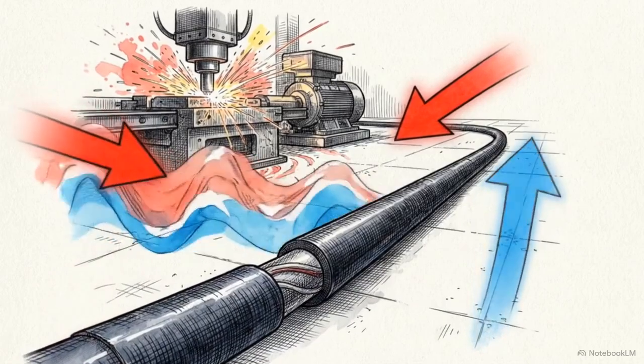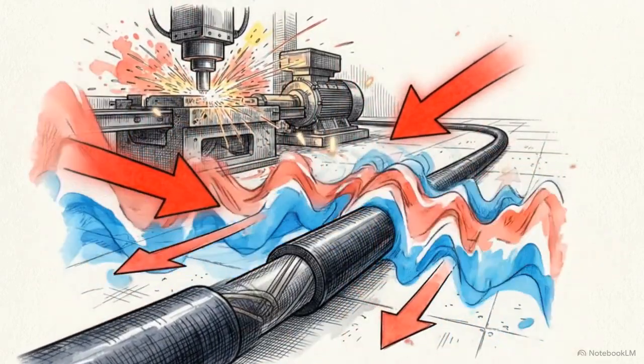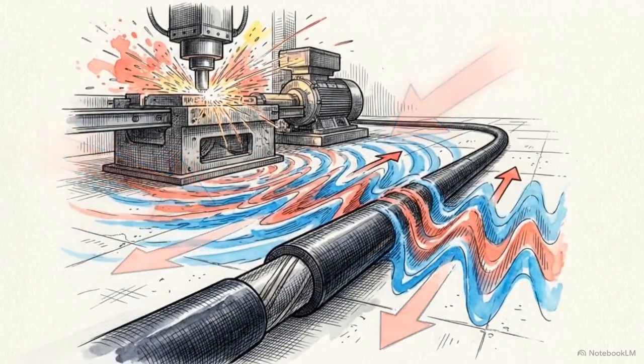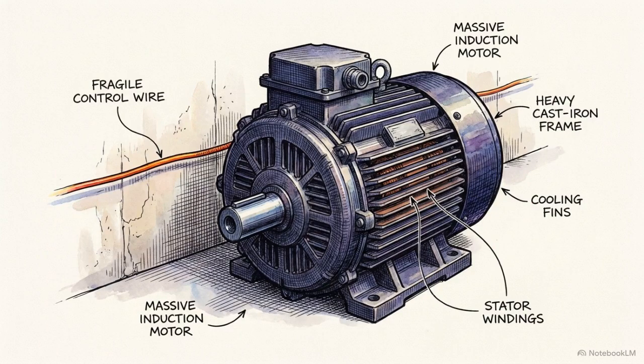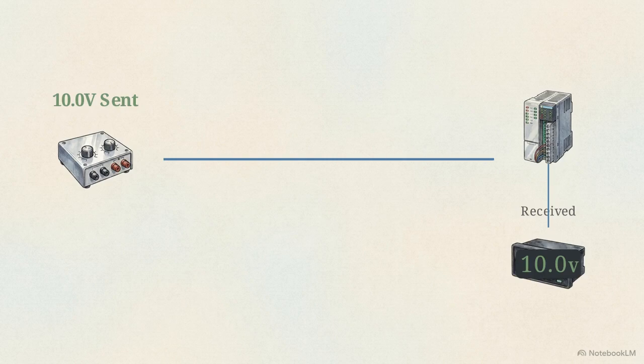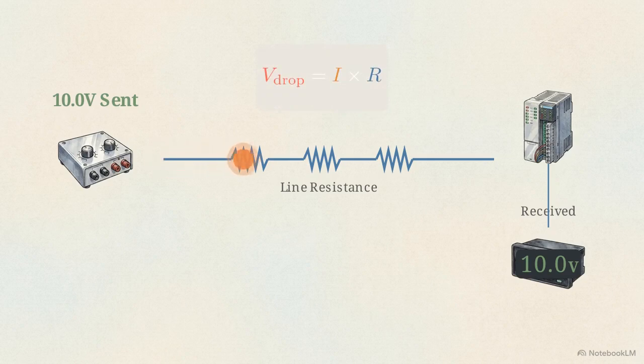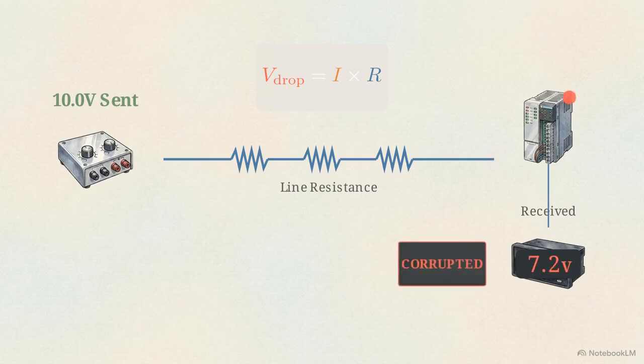Heavy machinery, large motors, and variable frequency drives constantly blast the area with invisible electromagnetic interference. If we try to transmit this pressure data using a standard 0 to 10 volt signal, we immediately run into a physics problem. This diagram illustrates a voltage source pushing a signal through a long wire. Because the wire itself has natural series resistance, Ohm's law dictates that we lose energy along the way. By the time the signal reaches the controller, that line resistance has caused a voltage drop, corrupting the original measurement.